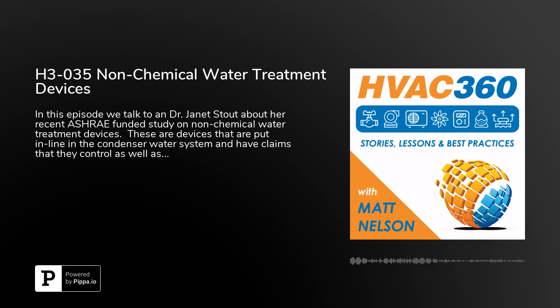The ultrasonic device makes a claim for microbiological control by something called acoustic cavitation. Essentially what they're saying is that certain types of bubbles are produced by the device and that the bursting of those bubbles near bacteria can kill them. And then the last type of device is the hydrodynamic cavitation device. That is the collision of water streams creating vortices, which drives out scale, and colliding under high pressure somehow ruptures bacteria. So those are the devices and the mechanisms of action that the device manufacturers claim.